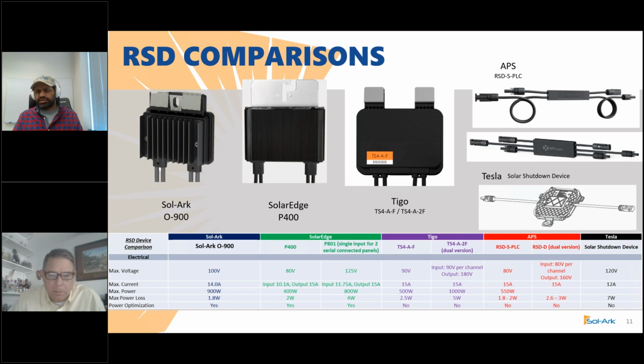The Sol-Ark is just a device that you connect a rapid shutdown button to - any kind of switch you like that's in a normally open position. When you activate the switch and close the circuit, the Sol-Ark goes into rapid shutdown mode and stops providing AC output to the transmitter circuit. The transmitter then stops sending the keep-alive signal, which shuts down the solar panels, and that's how you meet your NEC code requirements.